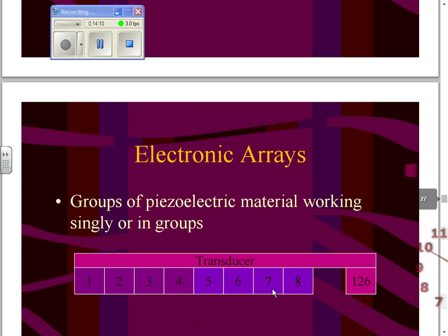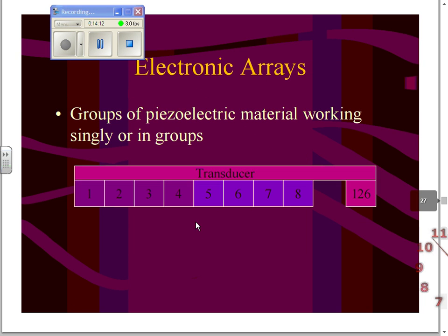Now, the actual machine is made of a transducer, which has the various piezoelectric crystals aligned. So what happens normally is the first one will be pulsed, then the second, then the third. The first one will send its pulse down, it gets switched off, and when the sound wave comes back, that signal is processed. By then, one of the others is firing. So they pulse in turn through the crystals. The crystal becomes a sound source, and then a little bit later it becomes the detector.